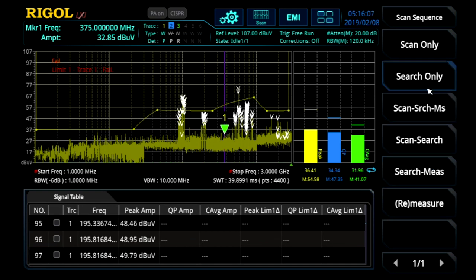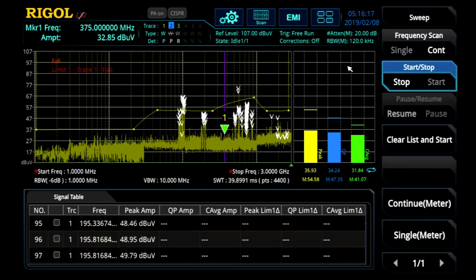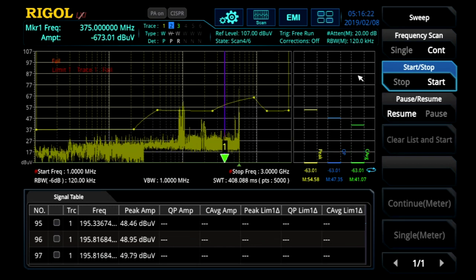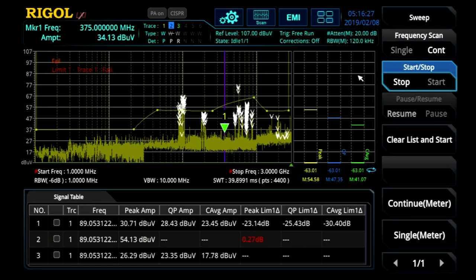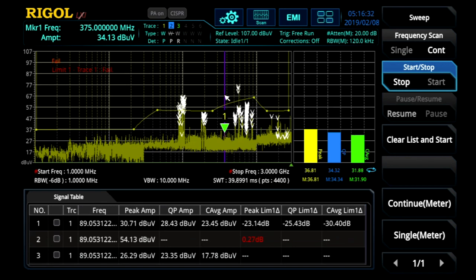The scan sequence is the critical operation area. You can do scans, search for signals in the signal table, do measurements, or do all of them together. Here we're going to do a little bit of everything. From the sweep menu, when I hit start, it scans and looks at peaks against those limit lines and against the peak detector areas. We've highlighted a key area at about 375 MHz, which is a harmonic coming off of our test device, and we're able to do real-time measurements on multiple detectors of that exact frequency.